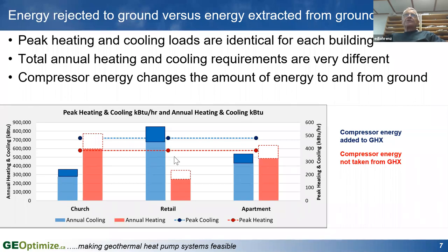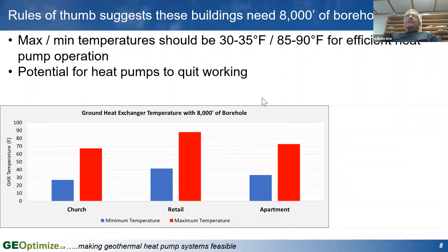This is a lot more unbalanced. The retail store rejects so much more heat into the ground than it pulls from it. This would be called a heating dominant project, or cooling dominant project, I'm sorry. This one would be a heating dominant project because you're extracting more heat from the ground, even considering the compressor energy, than you're dumping into it. So what that means, if you look at a typical rule of thumb, the temperature range that this system is going to operate at, the church, for example, will get down to, after about 10 years of operation, below about 26, 27 degrees Fahrenheit. So that's below freezing. That's starting to reach the point where the heat pumps are maybe not going to work very well. Retail store, on the other hand, is going to get up to close to 90 degrees. And again, on the other side, when you're cooling that much, it's more difficult to reject heat into something that's already 90 degrees than it would be in a church where the temperature barely hit 65 degrees.